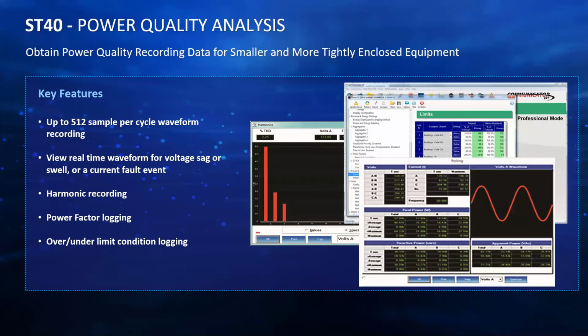You can look at your power factor to make sure your power factor is not too low. We always see that you want to keep your power factor in about a range of 0.8 to 0.9, because that's really a measure of how efficient your system is. And you can also look at your over or under limit conditions. All of these screenshots are from our basic version of the software. And again, you can use the Energy PQA. You can use your phone, your laptop, your iPad, and just go into your browser and look at all of this data. It is also available on the cloud solution Energy PQA as well.